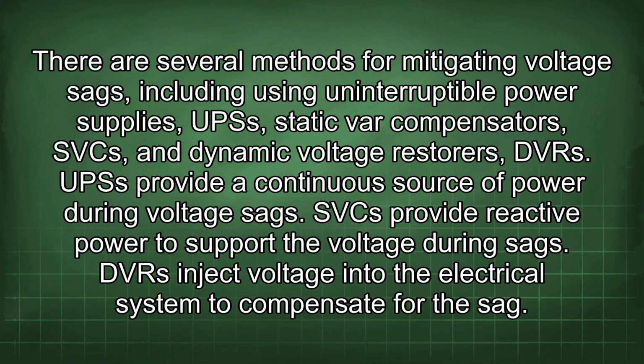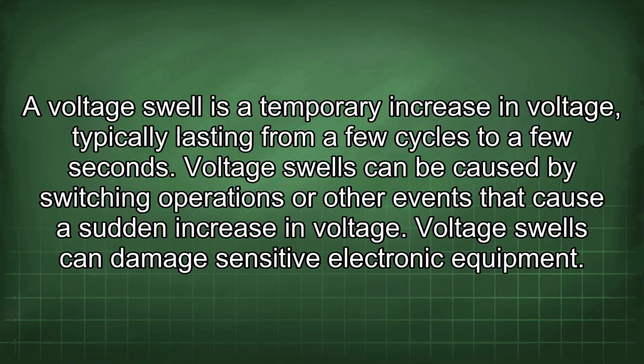There are several methods for mitigating voltage sags, including using uninterruptible power supplies, UPSs, static var compensators, SVCs, and dynamic voltage restorers, DVRs. UPSs provide a continuous source of power during voltage sags. SVCs provide reactive power to support the voltage during sags. DVRs inject voltage into the electrical system to compensate for the sag. A voltage swell is a temporary increase in voltage, typically lasting from a few cycles to a few seconds. Voltage swells can be caused by switching operations or other events that cause a sudden increase in voltage. Voltage swells can damage sensitive electronic equipment.